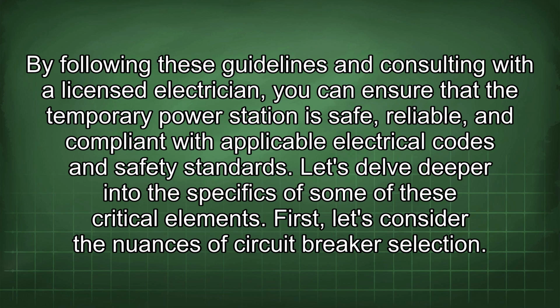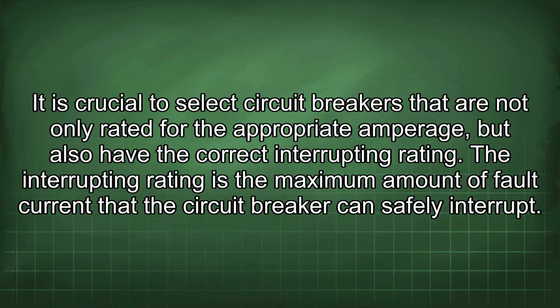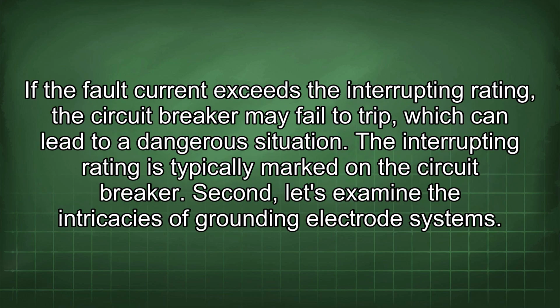Let's delve deeper into the specifics of some of these critical elements. First, let's consider the nuances of circuit breaker selection. It is crucial to select circuit breakers that are not only rated for the appropriate amperage, but also have the correct interrupting rating. The interrupting rating is the maximum amount of fault current that the circuit breaker can safely interrupt. If the fault current exceeds the interrupting rating, the circuit breaker may fail to trip, which can lead to a dangerous situation. The interrupting rating is typically marked on the circuit breaker.